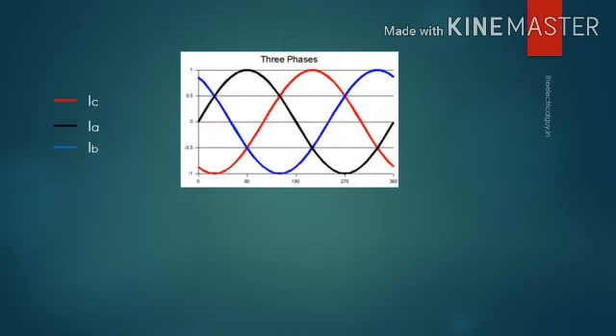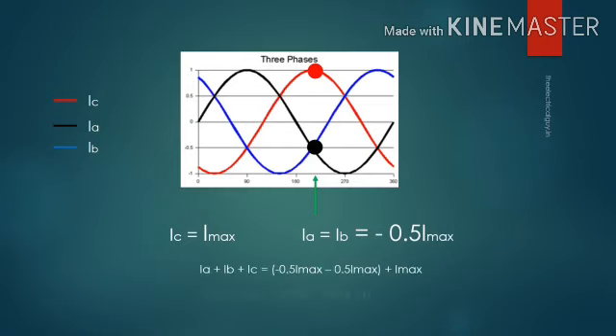Now, if you observe the diagram carefully, you will find that the sum of return currents is 0 at every instance. For example, at the instance corresponding to 240 degrees, IC is equal to maximum, and IB and IA are equal to minus 0.5 Imax. So if we add these return currents, we will get the sum equal to 0, and this is true for every instance. We can therefore remove the neutral conductor without affecting the voltage or current in the circuit. So we have reduced the number of conductors from 6, which was the initial stage, to 3. That is a 50% saving in conductor cost.